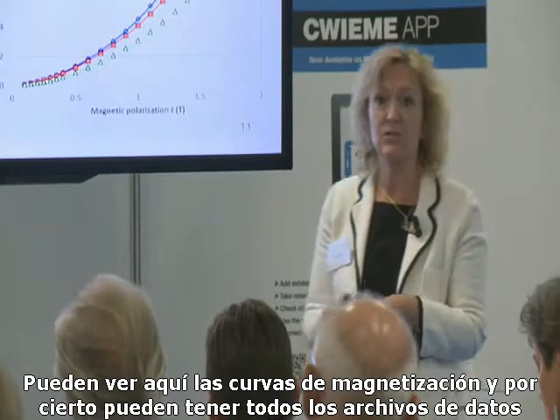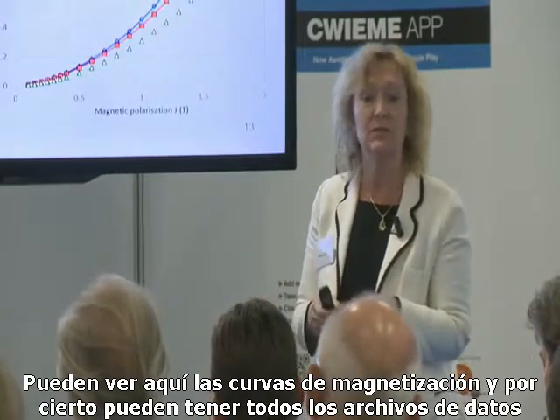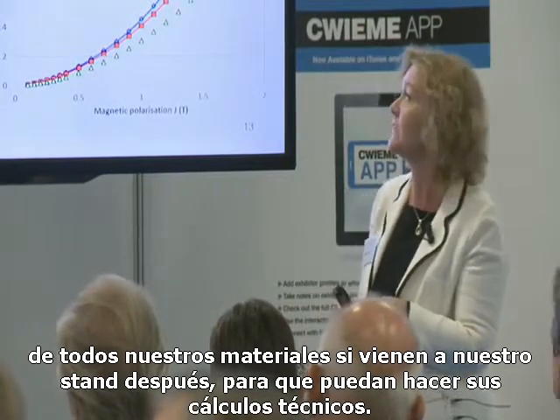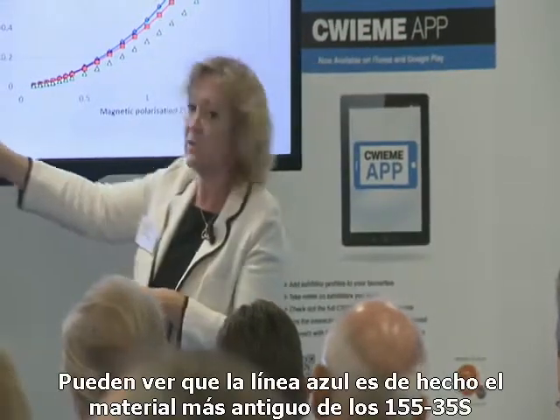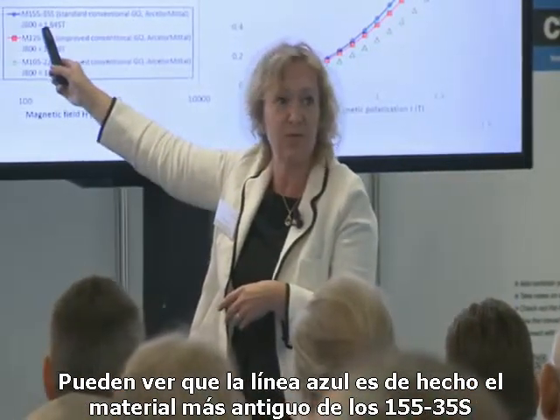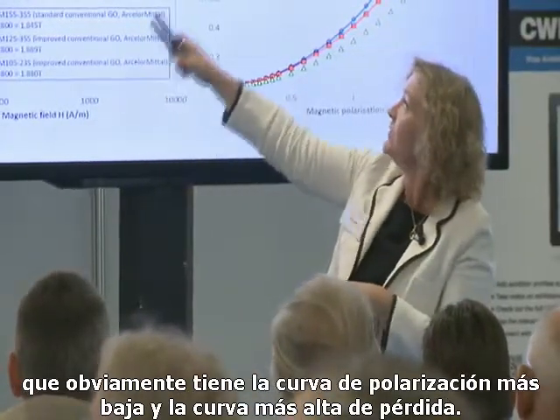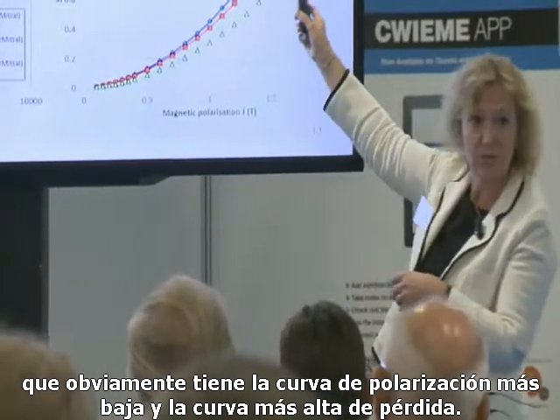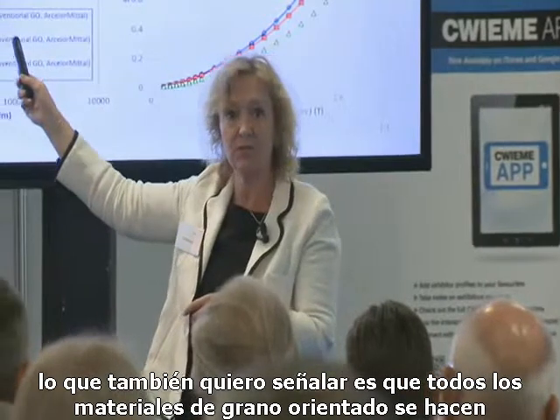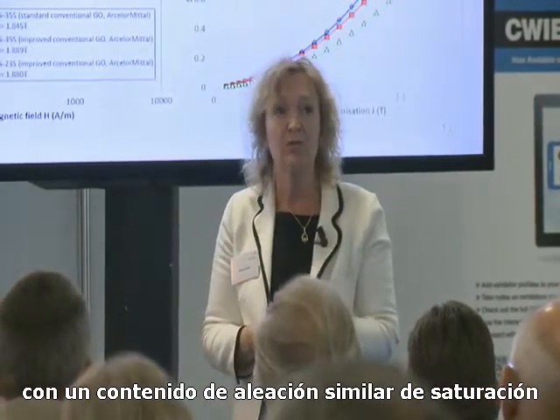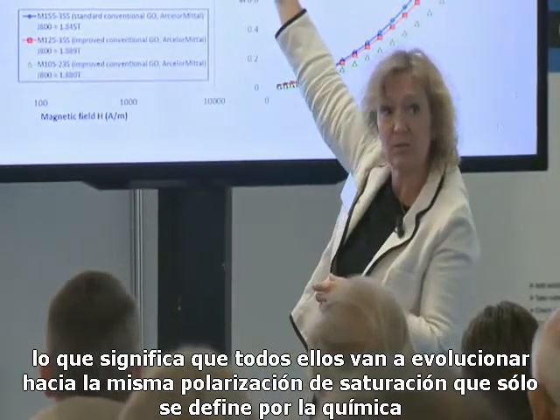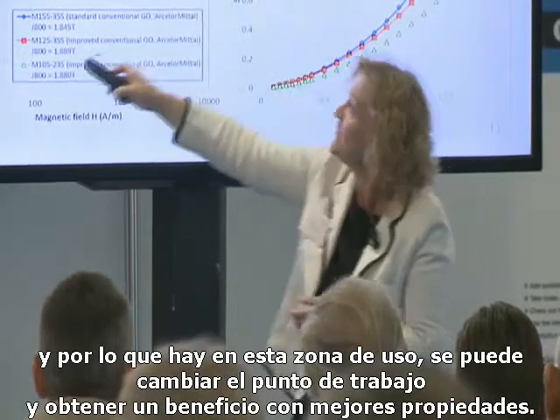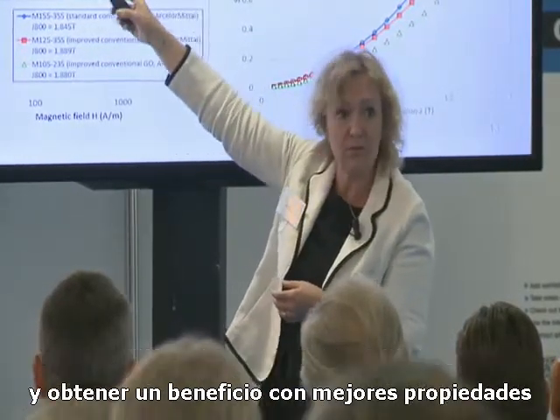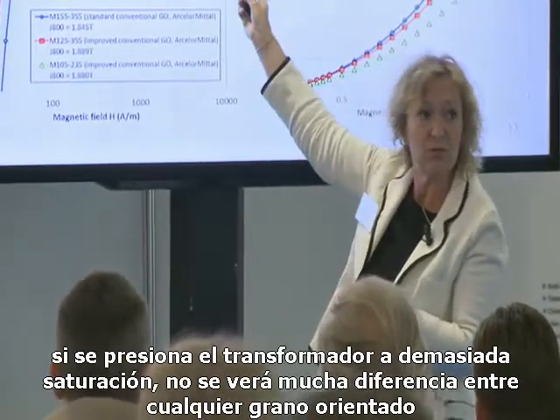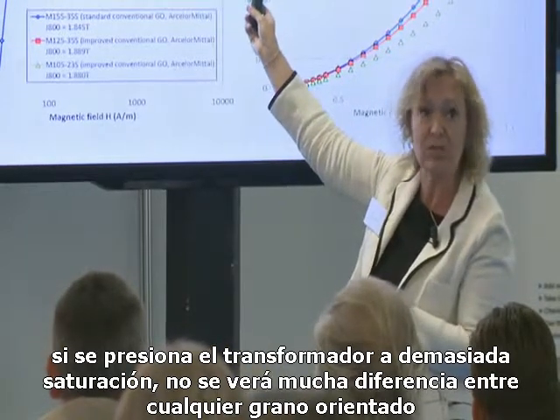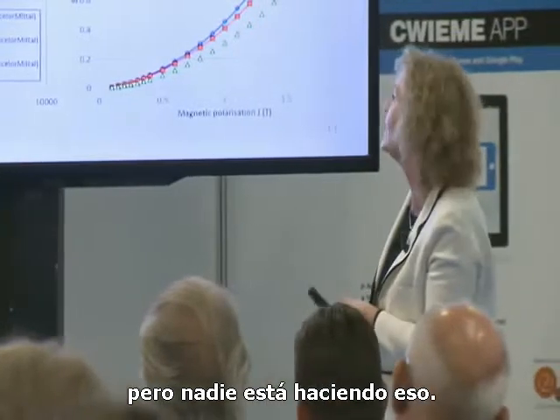You can see here the magnetization curves, and by the way, you can get all the data files from all our materials if you come to our stand afterward, so you can do your own technical calculations. The blue line is the older material, the 155-35S, which has the lowest polarization curve and the highest loss curve. I also want to point out that all the grain-oriented materials are made with a similar alloy content, meaning they will all evolve toward the same saturation polarization, which is defined only by the chemistry. So in this area of use, you can change the working point and benefit from the better properties. If you push your machine or transformer too far into saturation, you won't see much difference between any grain-oriented material, but nobody normally does that.